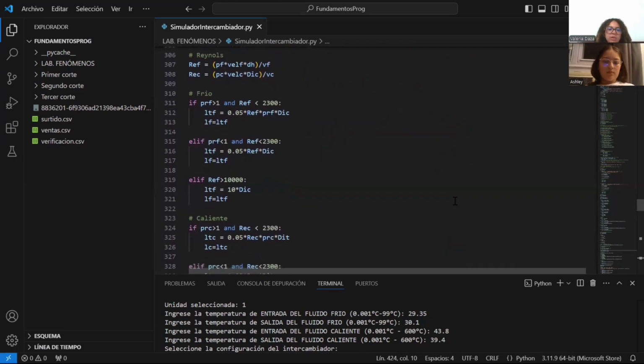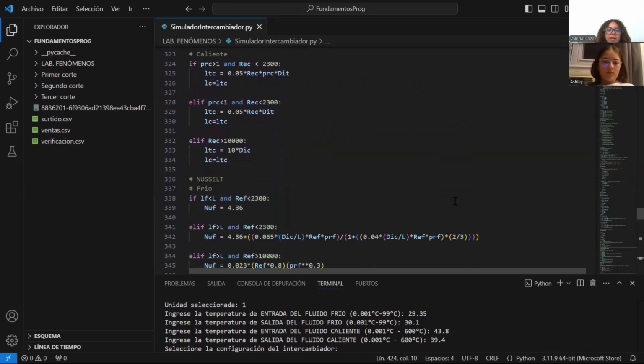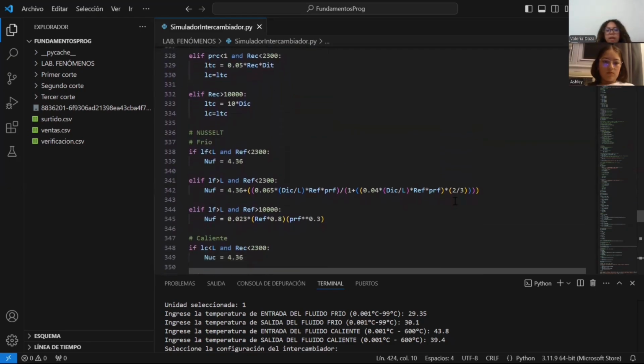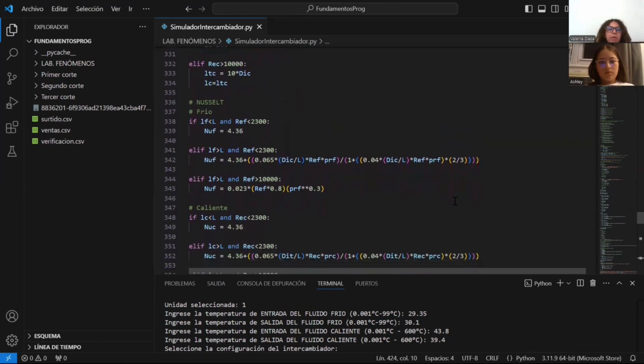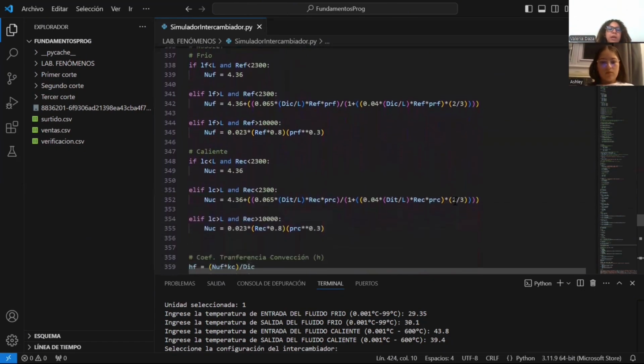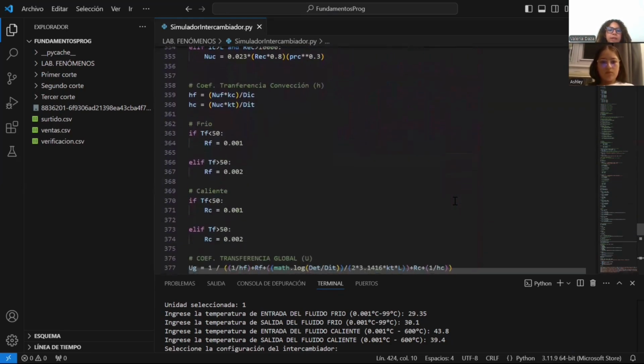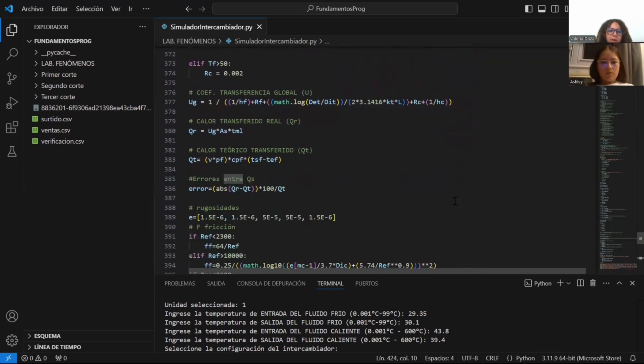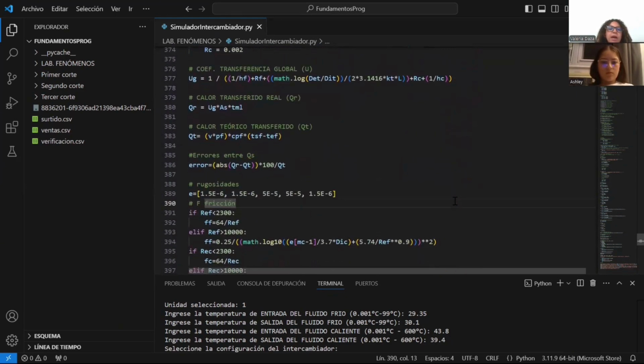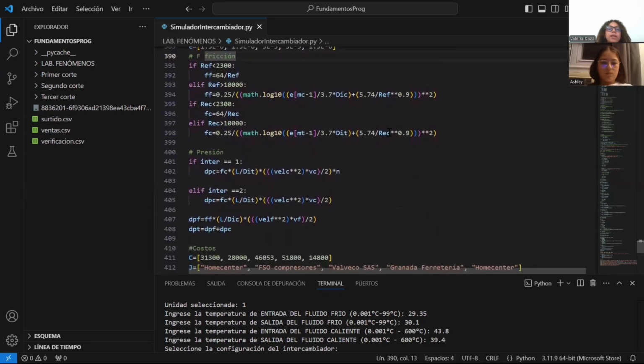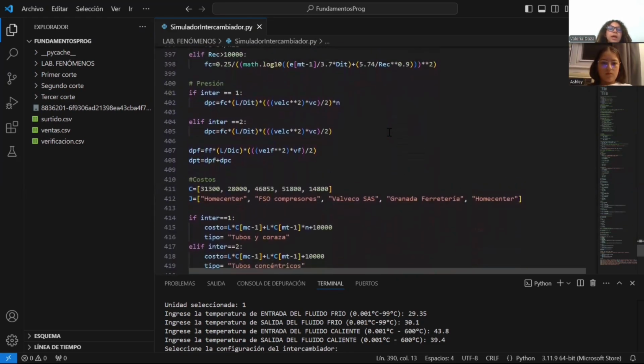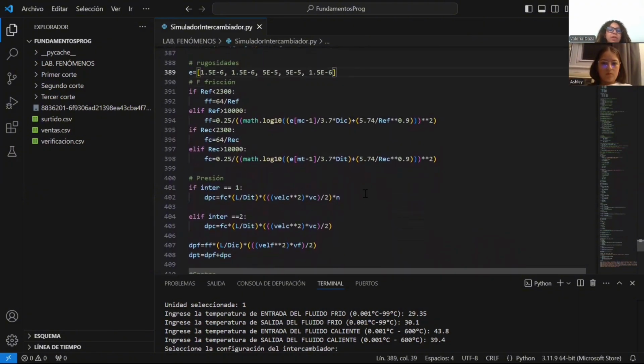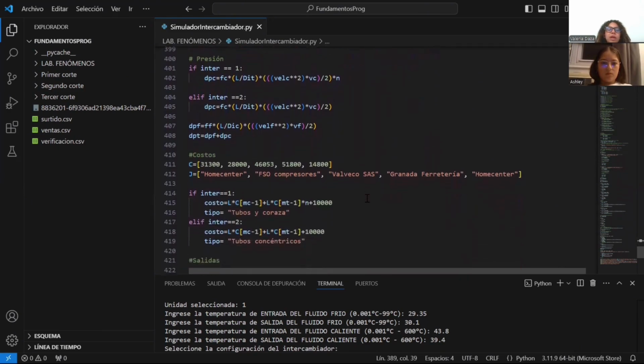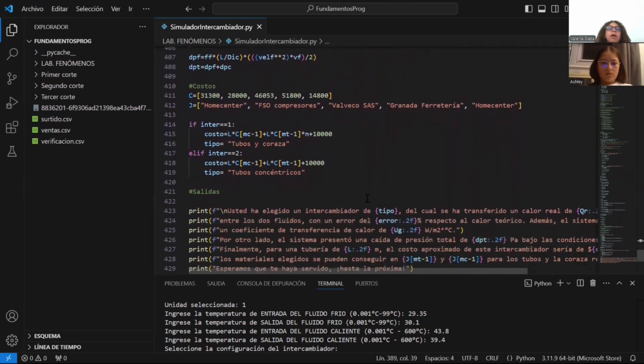Additionally, a Reynolds number was estimated for each of the flows, and then some conditionals were made for calculating each length according to the regime and the Prandtl number. Then we were able to estimate the Nusselt number according to this formula, and finally we were able to take the convection coefficient and then a global coefficient according to this formula, and finally the heat transferred, the real one and the theoretical one. Lastly, for the pressure drop, here we had the roughness and we made some vectors for this. Finally, we estimate one pressure drop in the inner tube and another in the outer tube, and then we added them for the total pressure drop. For the cost, here are the formulas, and finally the final answer gets to the user.